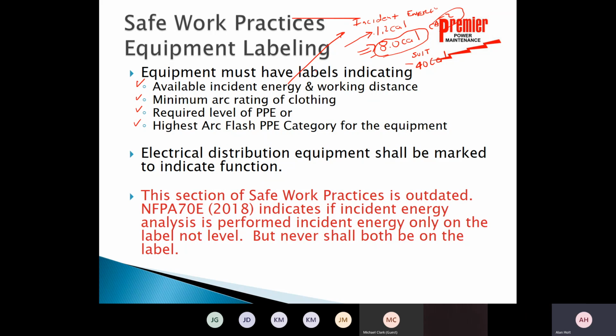Okay. So those are the incident energy ratings that we need to look at on the stickers. And then the working distance, okay, that's a little misleading. The label also has to have the arc flash boundary. The arc flash boundary should be given in inches. I wish it was in feet sometimes, but it's given in inches. So you're going to have an arc flash boundary. If you cross that arc flash boundary, you don't necessarily have to have an arc flash suit on or arc flash clothing. The key is you cross that boundary and there's somebody working within the limited approach boundary with tools in their hand, or there's cause to suspect that there is a potential arc flash. Okay. So that's kind of a definition.